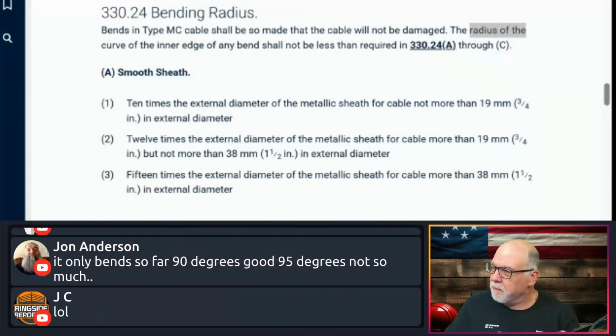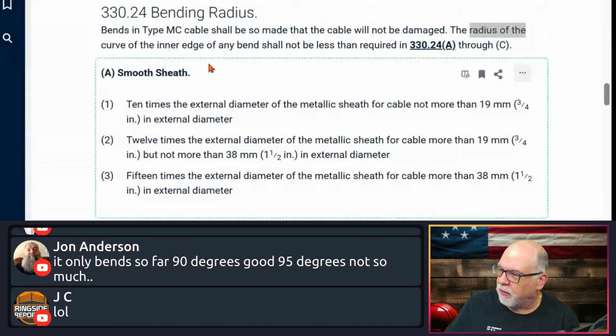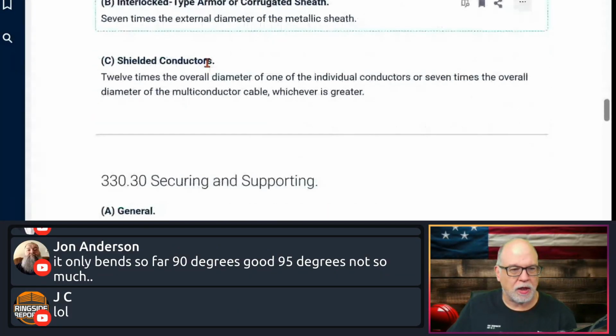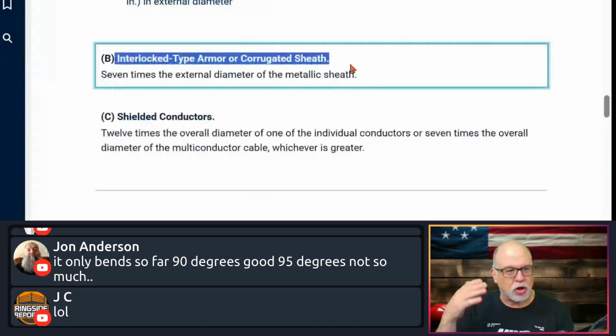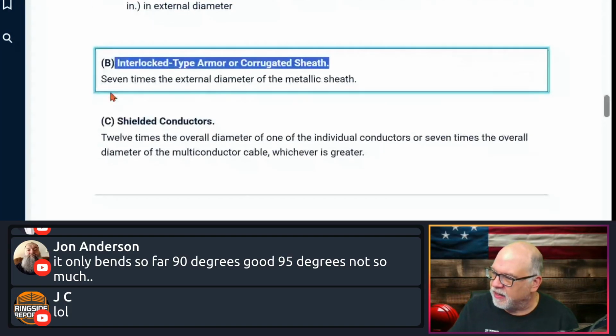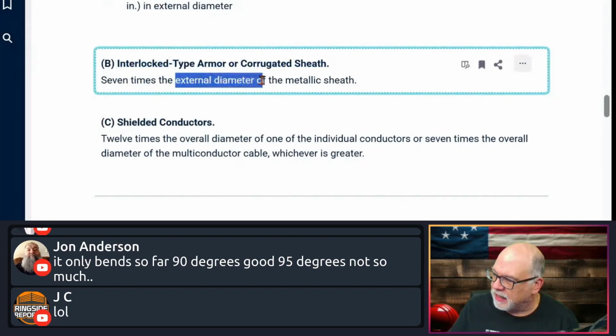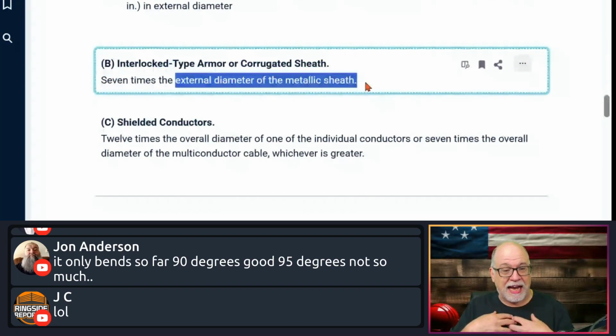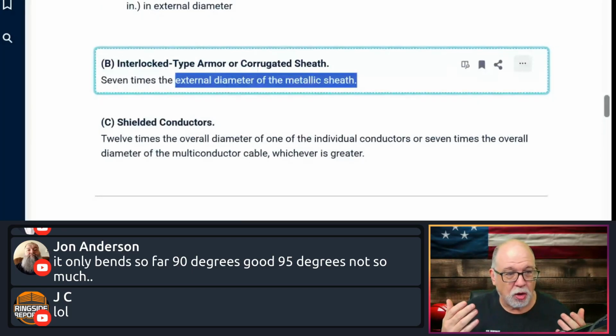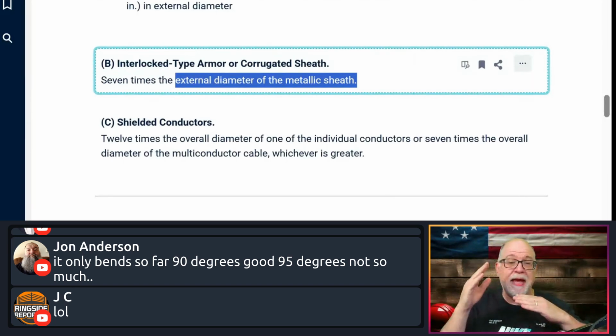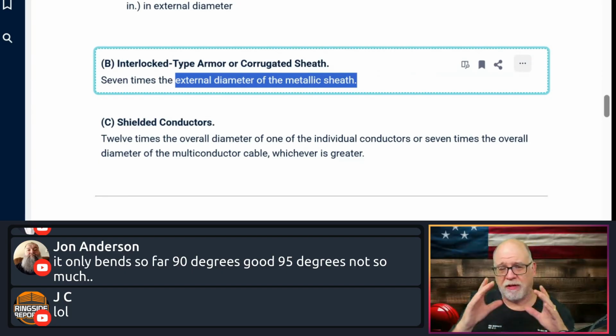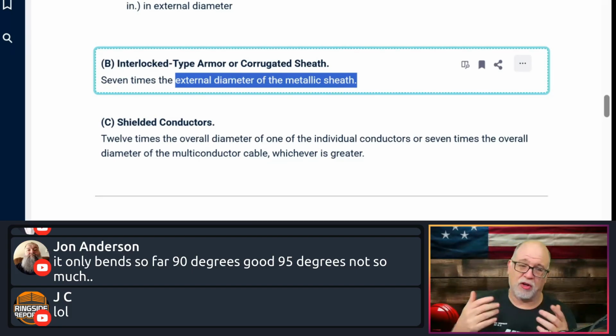All right, back to the bending radius. Okay, that's smooth. So now for interlocked and corrugated, or continuous welded, which could be followed under the corrugated moniker, it's 7 times the exterior diameter of the metallic cable. So for the normal interlock that you use every day of the week, all you're going to do is take the OD, the external diameter, and multiply it times 7. That is the maintained bending radius on that MC. Basically it's like bending it around a baseball. Don't go further than that, or get to the point where it even looks like you're going to damage the armor.